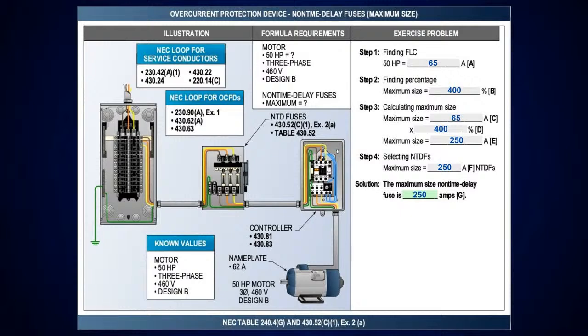It's going to tell you that if I have non-time delay fuses, I can increase those. And it says, shall be permitted to be increased. And listen to what it says, but shall in no case exceed 400%. So it says I can't exceed. That means I've got to do what? Drop down. And that's another percentage that's above the 125%. So if I take the 65 amps at 400%, that's going to give me 260 amps. And you'll need a 250 amp overcurrent protection device.